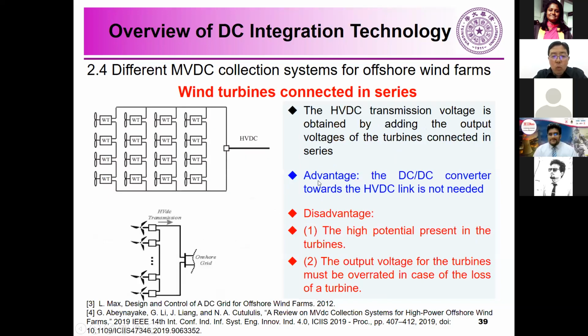Also, another way is the wind turbines can be connected in series. This has the advantage that the DC-DC converters towards the HVDC link are not required, but the disadvantages are also obvious. The high potential is present in the wind turbines, and the output voltage of the turbines must be overrated in case of the loss of a turbine.